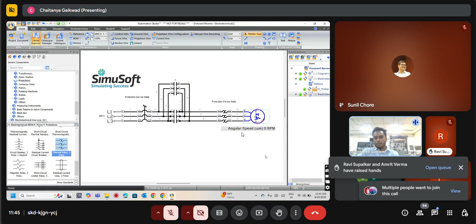That's much easier as it is. The middle one I will keep the same. So my power circuit is now ready. In my power circuit I have a 3-phase power supply, a protection device, a circuit breaker, my two contactors for controlling the direction by switching the supply, and another protection device, my overload relay, to protect my motor from overheating and overcurrent.